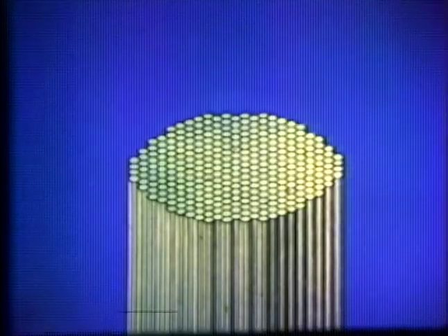364 fissile fuel assemblies constitute the core. A total of 24 hexagonal channels are reserved for the rods which control the chain reaction. 233 fertile fuel assemblies complete the core blanket assembly, containing a total of 5 tons of plutonium and 110 tons of depleted uranium. The entirety is surrounded by steel shielding elements.